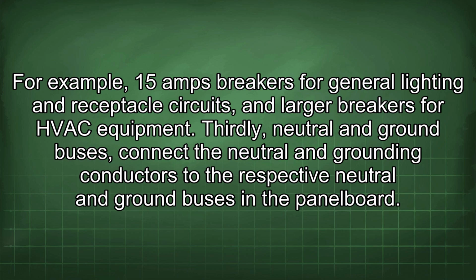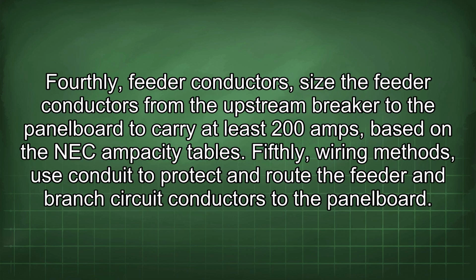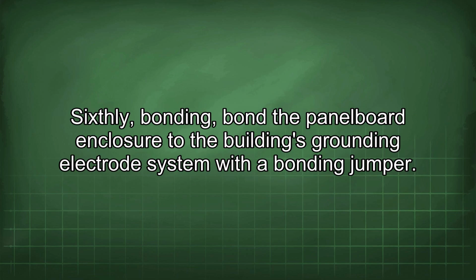Thirdly, neutral and ground buses. Connect the neutral and grounding conductors to the respective neutral and ground buses in the panelboard. Fourthly, feeder conductors. Size the feeder conductors from the upstream breaker to the panelboard to carry at least 200 amps, based on the NEC ampacity tables. Fifthly, wiring methods. Use conduit to protect and route the feeder and branch circuit conductors to the panelboard. Sixthly, bonding. Bond the panelboard enclosure to the building's grounding electrode system with a bonding jumper.